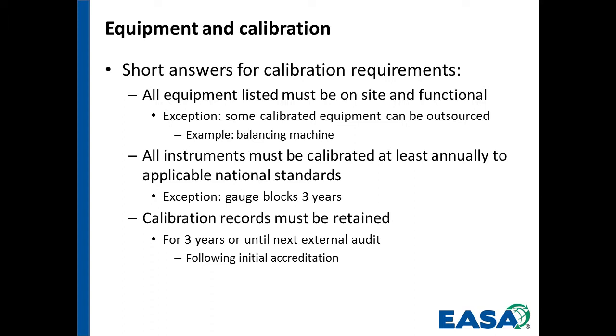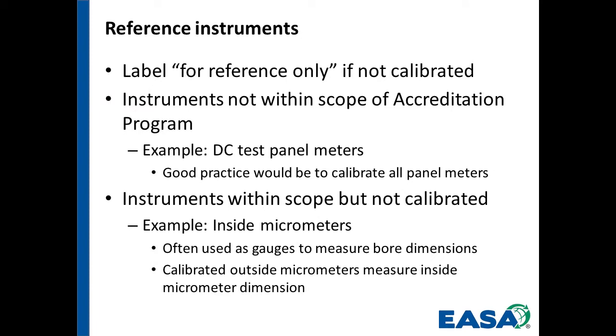Annual calibration, mentioned that. Record retention: you need to have your records on file for 3 years or until the next external audit, and that's following the initial accreditation. If you go into the accreditation program and you purchase a brand new core tester, you can't have a calibration record going back 3 years. It's not been there that long. So we're trying to make it realistic and say, after the initial accreditation, whatever's in there is grandfathered in. From there on, you need to keep those records for at least 3 years, at least until the next external audit.